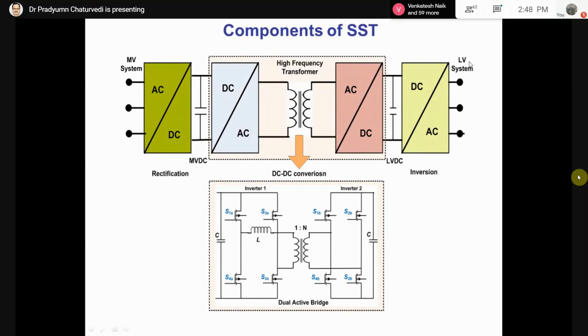Under different backend or DC or load and conditions, and under all input side power quality problems like sag, swell, and other things, this is an improved power quality converter, having efficient and high power density. Now this DC link is at one voltage level, like MVDC, around 10,000 volt DC. Invert this, use one HFT, again rectify this, use a second DC bus here at LVDC ratings, and if required then invert this to AC, otherwise stop at LVDC.